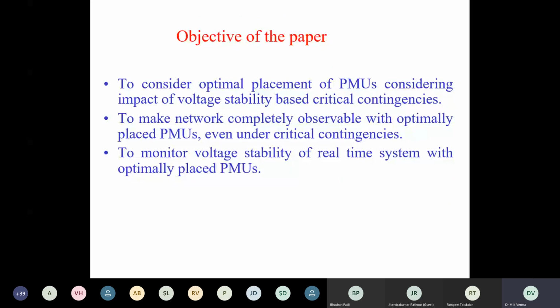So the objective of the paper was to consider optimal placement of PMUs, considering the impact of voltage stability under critical contingency. In order to make the network completely observable, the PMUs were to be optimally placed at certain locations. He has considered complete observability not only for the intact case but also in the critical contingency. And he considers the monitoring of voltage stability of a real-time system with optimally placed PMUs.